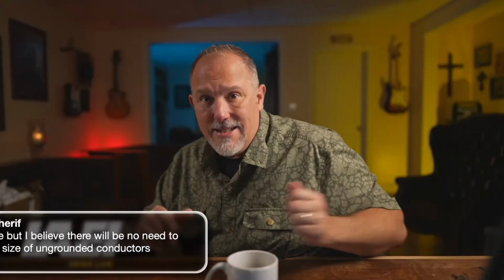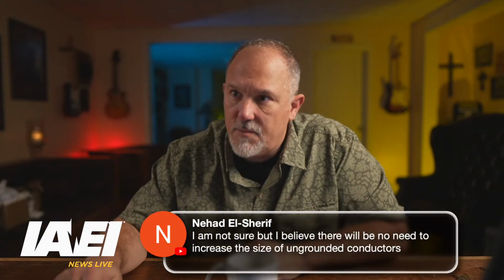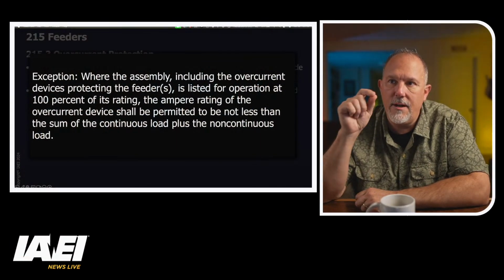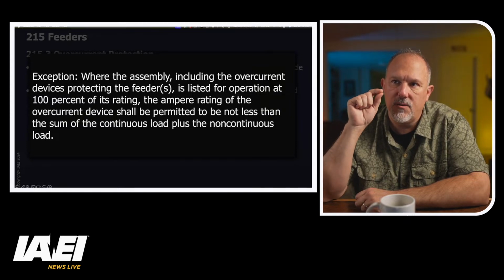So if you made a mistake in your load calculations, don't think that just by replacing the overcurrent protective device, you have solved your problem, because you may not have solved that problem at all. Make sense? So be careful of that. And we can use this exception, but it's not just about the overcurrent protective device. It's the equipment within which that overcurrent device is installed as well.